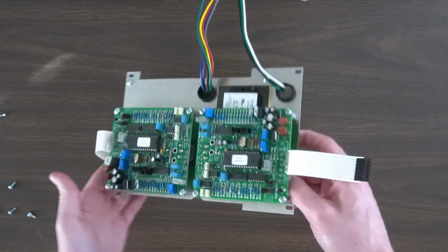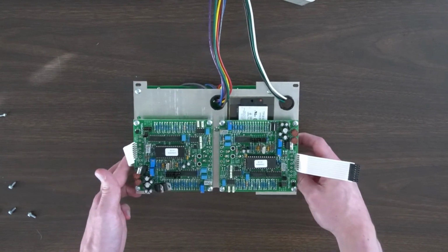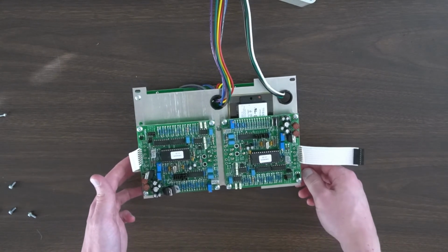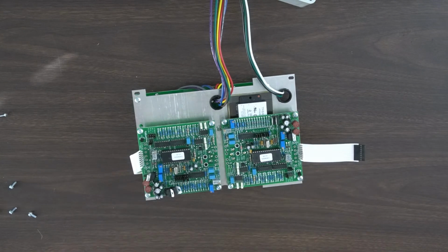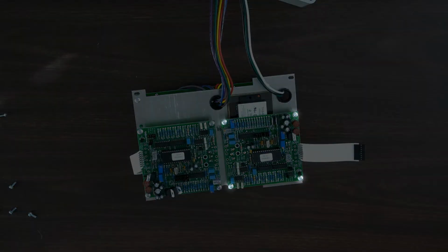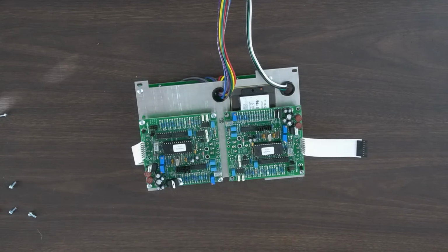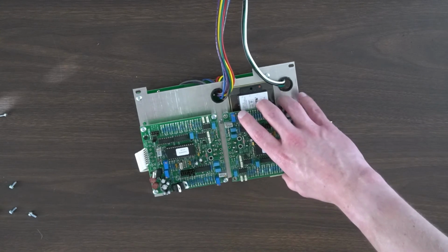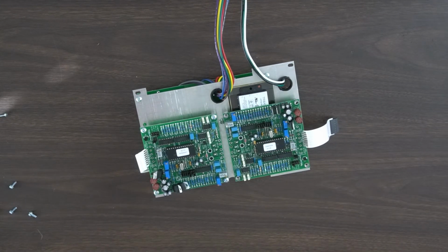Next, flip the unit over. Be careful not to scratch the display or bend the button and LEDs. Then remove the 4 screws on the sensor board. Take the new sensor board from the calibration kit and replace the existing sensor board. The old sensor board may be discarded.